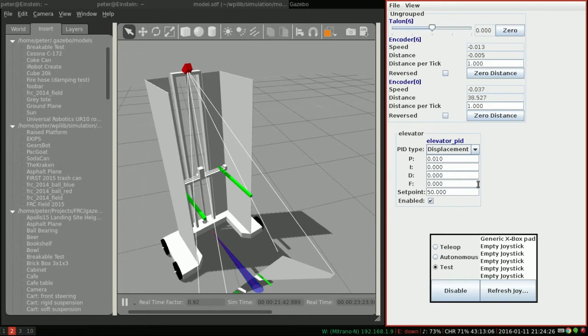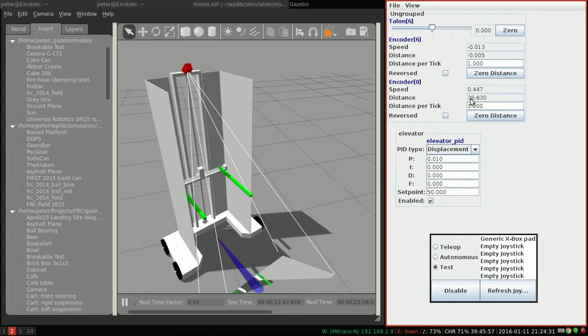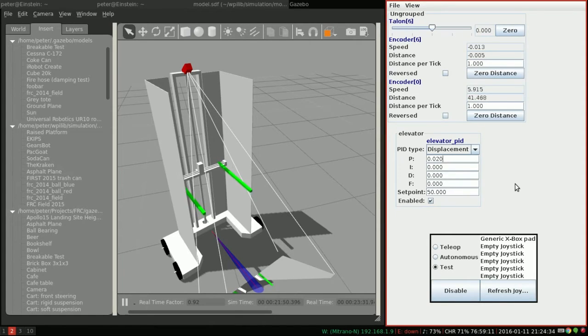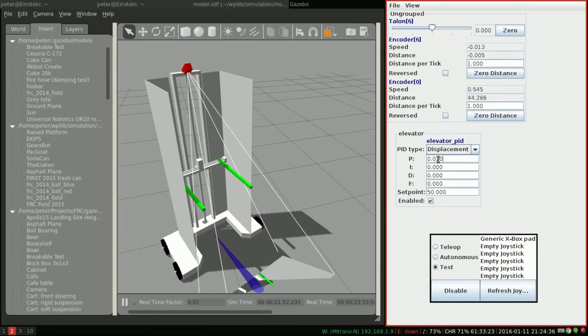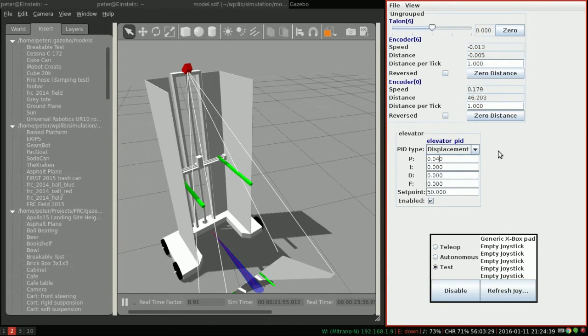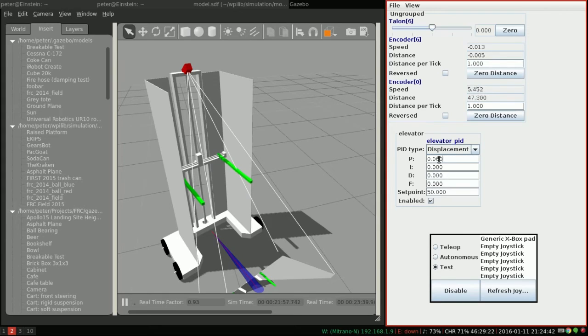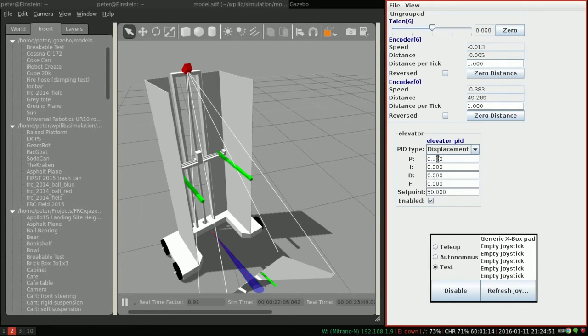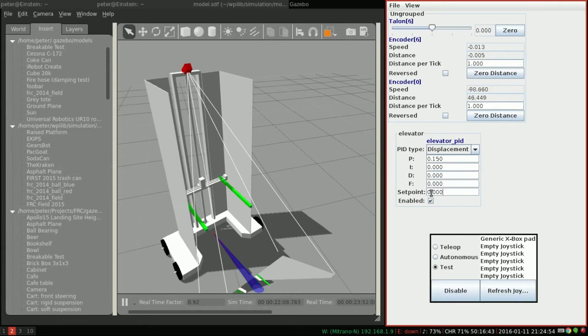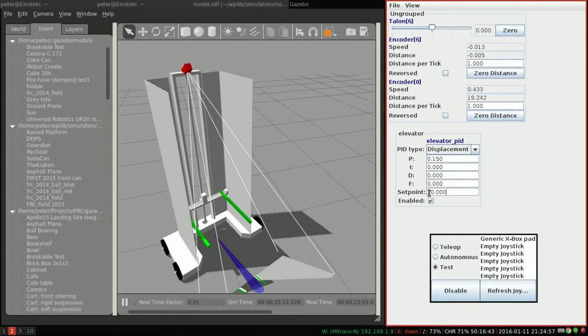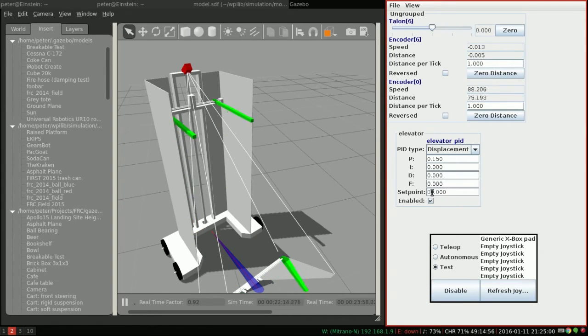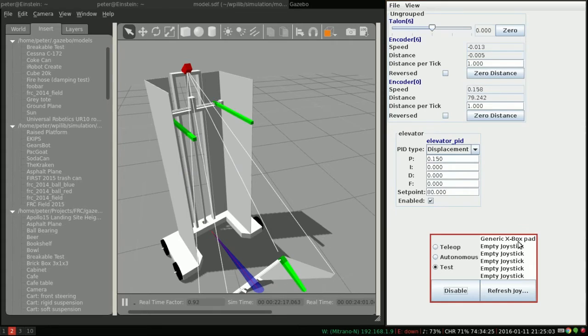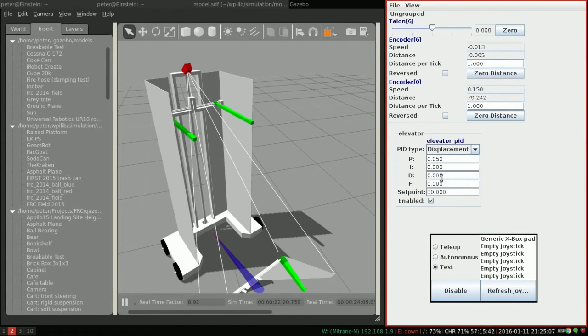So now you can see the problem we have. The set point is 50, but we've only reached 38. Now of course I can increase this and we'll get closer. But in order to increase it enough to get to our set point, which seems to be about that 0.1 I had earlier, in order to reach the set point, I'm now moving more quickly than I've specified. So here we have to do some actual tuning.